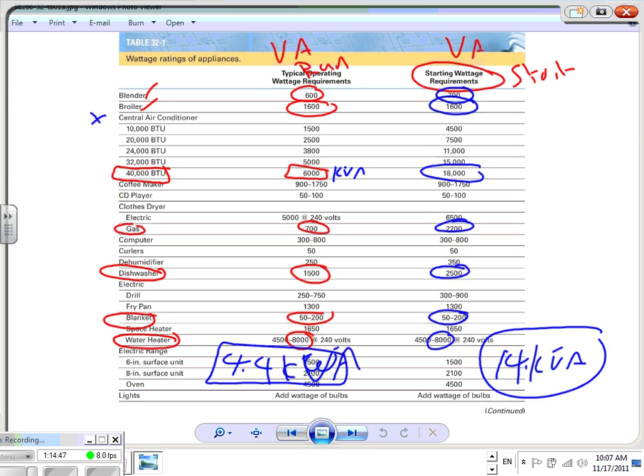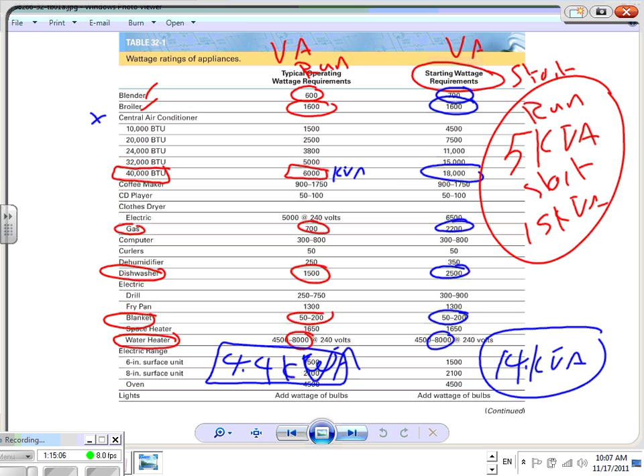Okay, add them up. In a case like this, here's what I'm going to go by. I'm going to go by a 5 kVA generator, this is the run, and the starting capability is 15 kVA. Done. What's the voltage? You need the voltage and frequency, depending on what your voltage and frequency are. We size a generator based on two things, running and starting current. Questions? Any questions, guys? This is very, very substantial when you work with generators. If you call any generator guy to size a generator, they ask you what's your load and what's the largest motor. They ask about the motors that you have, so they can be able to start that thing.